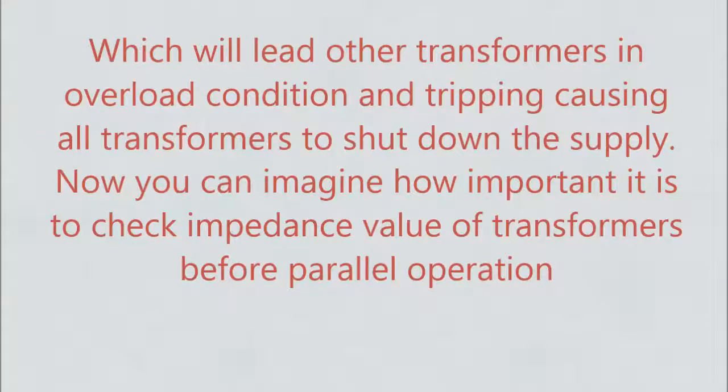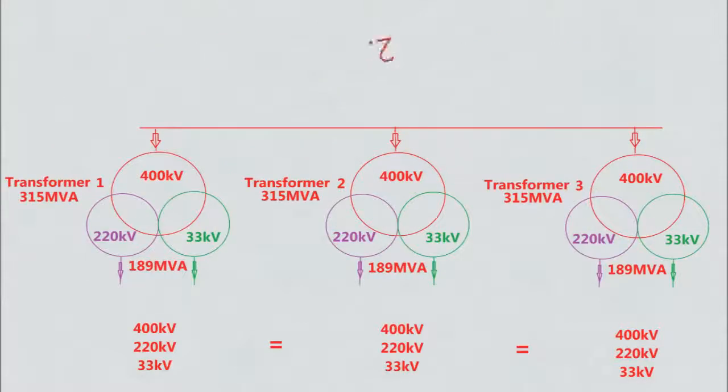This will put other transformers in overload condition and tripping, causing all transformers to shut down the supply. Now you can imagine how important it is to check impedance values of transformers before parallel operation. The second condition is that voltage ratings of the transformers should be the same. For example, a 220 kV transformer can be paralleled with another 220 kV transformer only, and not with one of a different rating.